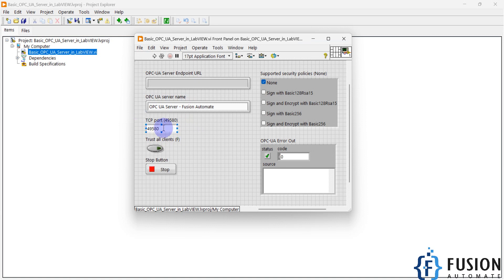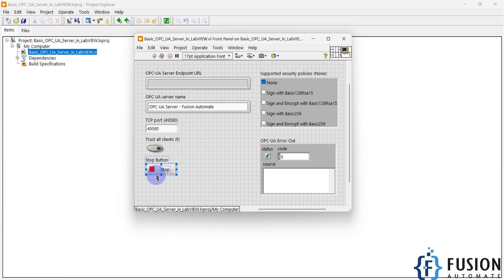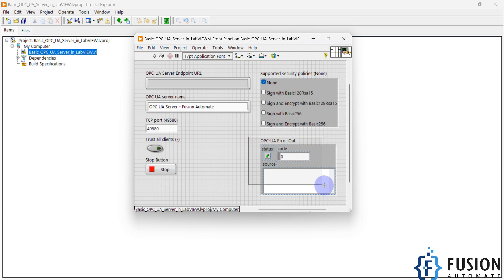Here is the TCP port number on which your OPC UA server will be started. You can change the TCP port number if needed. If you want to trust all clients, you can enable this option; if not, you can disable it. If you want to stop the server, click the stop button. You can also select which security policy is supported, and any errors will be displayed here.